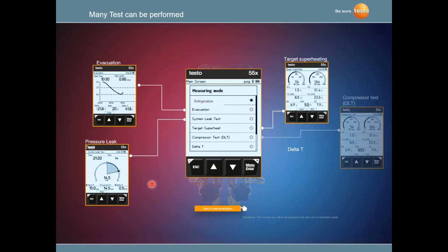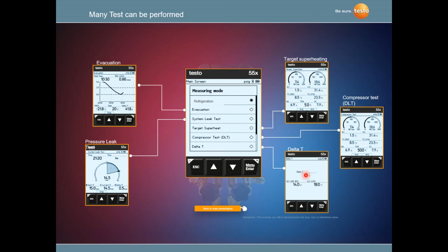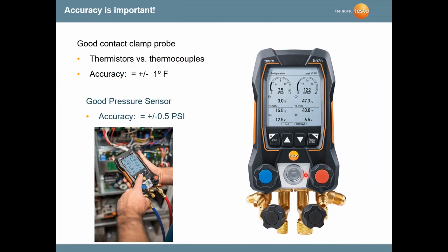Targeted superheat we talked a little bit about. We also can do a compressor test. Not only do we look at superheat and subcooling, but we can also look at the discharge line temperature on a compressor and get that simultaneously as we're reading the superheat and the subcooling. And certainly we could do a lot of different differential temperatures across coils and across filters, things of that nature.